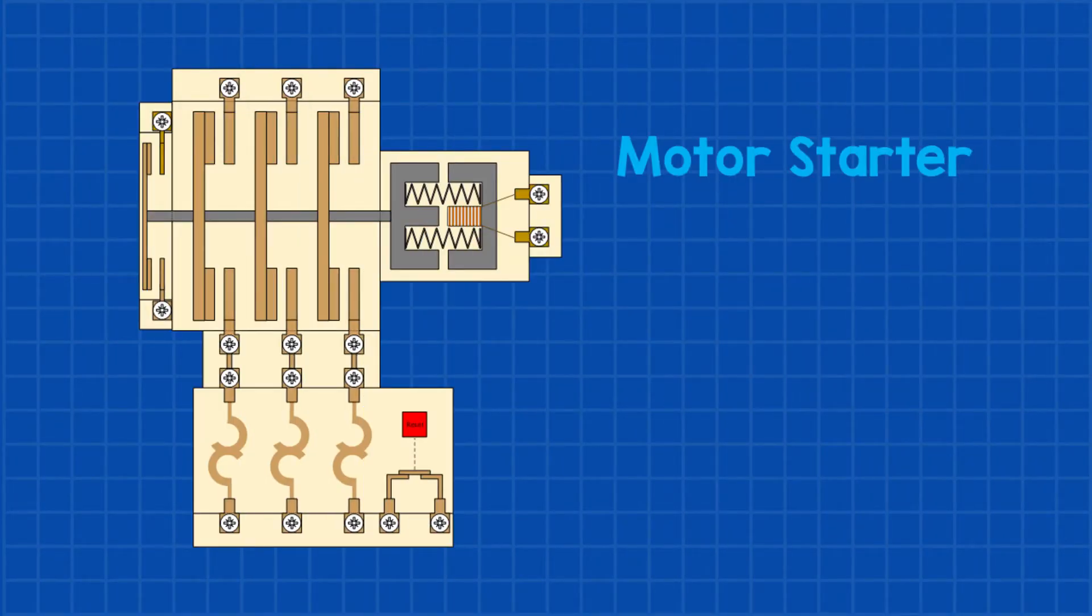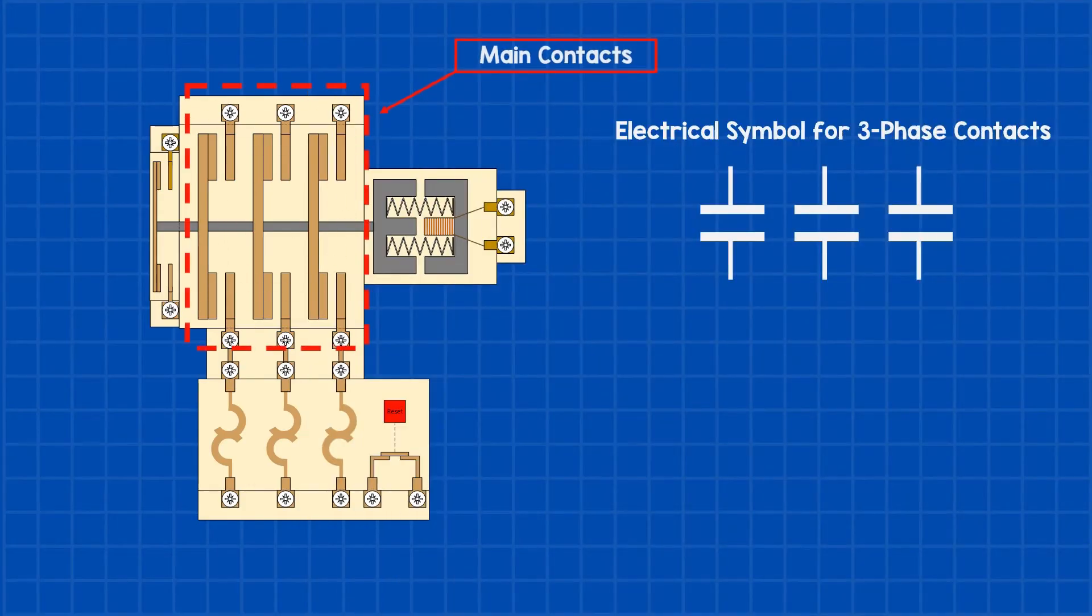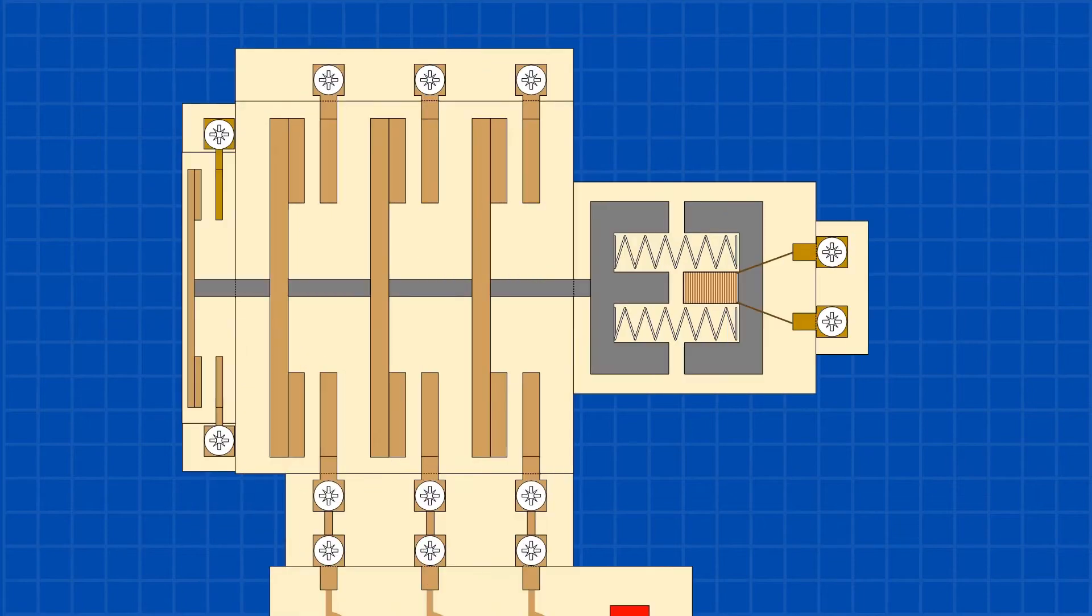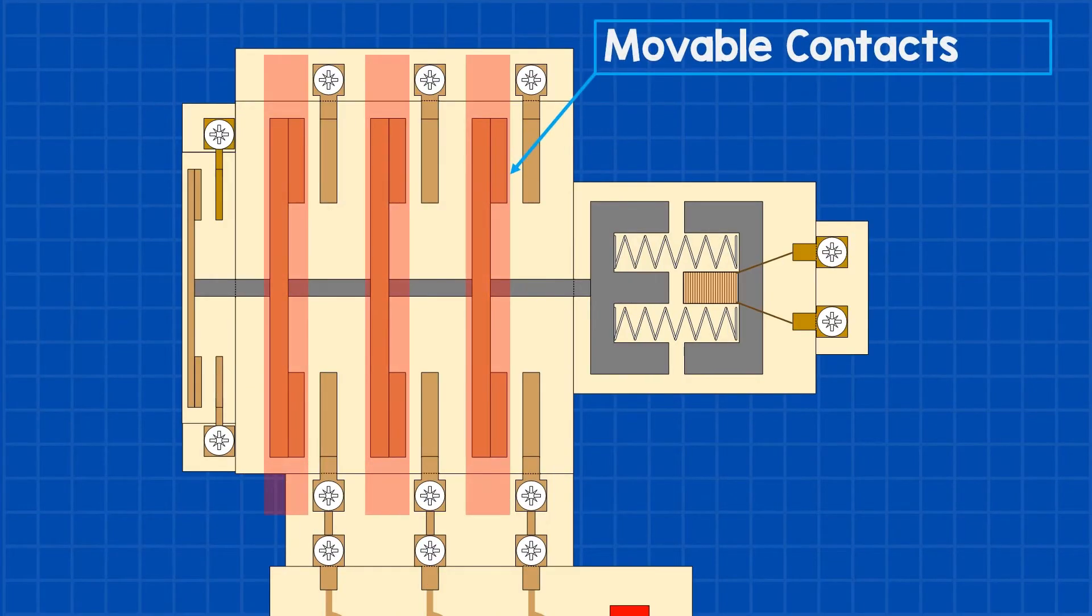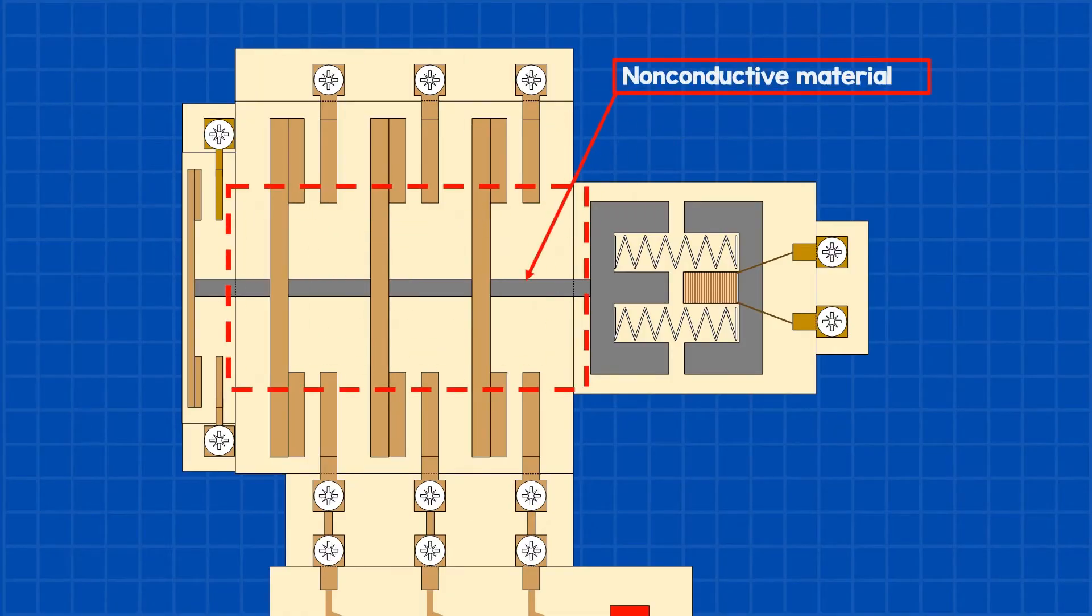But how does a motor starter work? First, the motor starter contains three sets of contacts that deliver power to the motor. Each set of contacts consists of a stationary and a movable contact. The movable contacts are attached to the coil with non-conductive materials, like fiberglass or reinforced molded plastic.